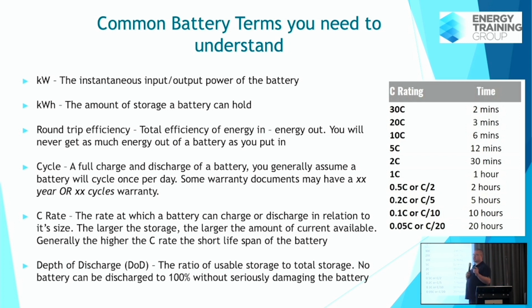The harder I charge and discharge my batteries, the hotter they get, and the hotter they get, the shorter their lifespan will be. We don't want our batteries thermal cycling all the time. So you'll find most batteries on the market are somewhere around the half C rate. If you're buying a 10 kilowatt hour battery, generally they're discharging at around 5 kilowatts max. That seems to be a pretty manageable C rate for most batteries, and it appears most manufacturers have settled on the fact that at half C, they expect their batteries to last the lifetime of the warranty they've given.